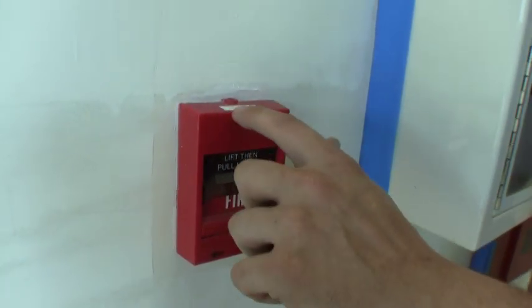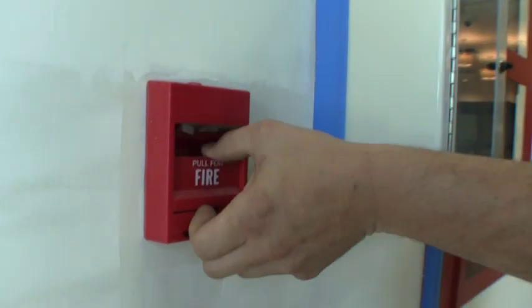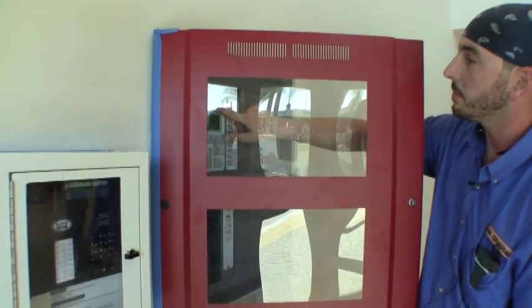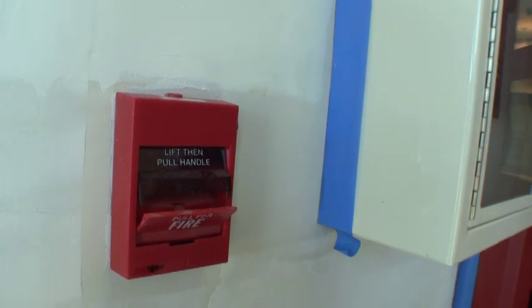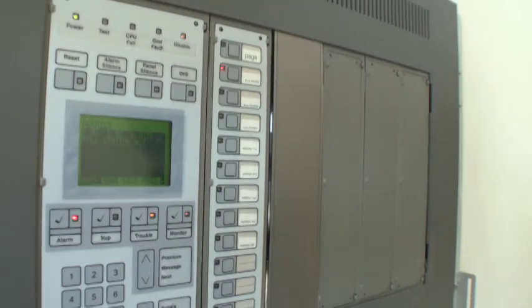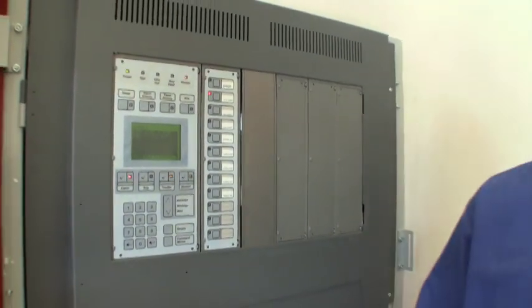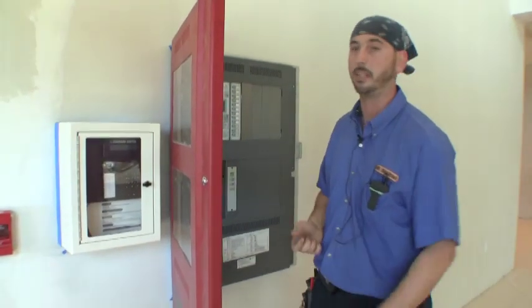Each device is labeled with its panel number, address, and location related to the system — each pull station, each smoke detector. So if we pull pull station 14-02-153, we get a message: pull station, entry vestibule. If we hit details, it'll give us the address 02-153 of that specific pull station that was pulled. It'll be the same thing for each device — smoke detector, pull station, flow switch — each has an independent address and each will relate back to its description of where it is in the building.